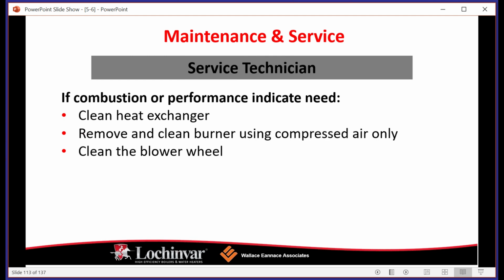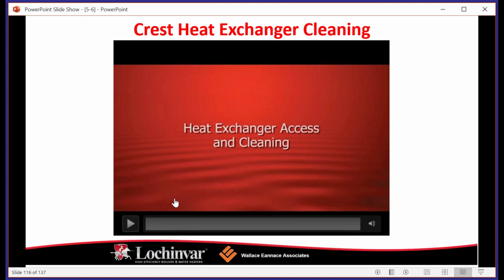Again, have one on hand in case you need it. But again, the flame rod and the igniter are going to be inspected annually, not necessarily critical that you replace it. If you pull it out and it looks like the day you put it in, it will continue to run. But always have spares, especially if you have a large commercial plant where you have a cascaded bunch of boilers, a big bank of boilers or water heaters. Always have extras on hand. Just best practice, and it'll save you a bunch of headaches.